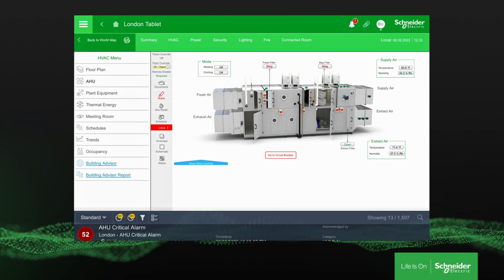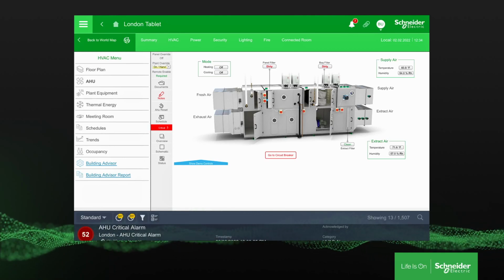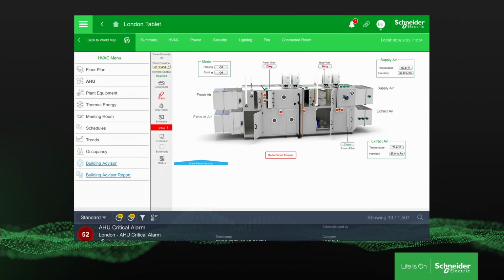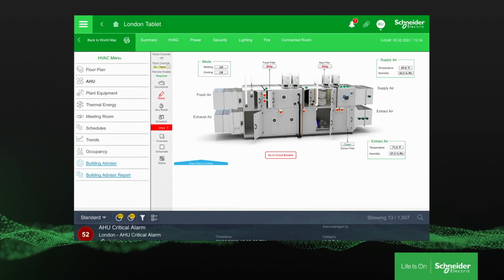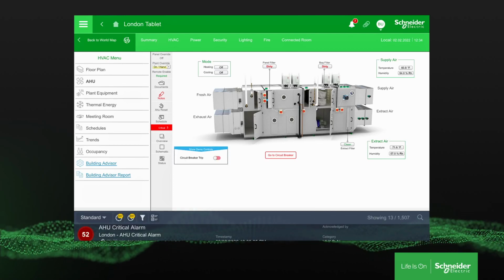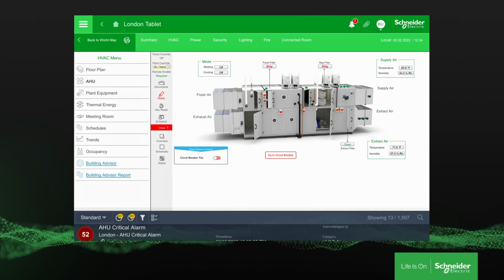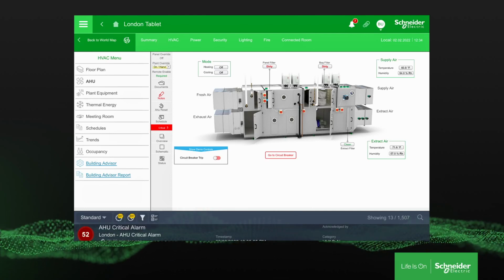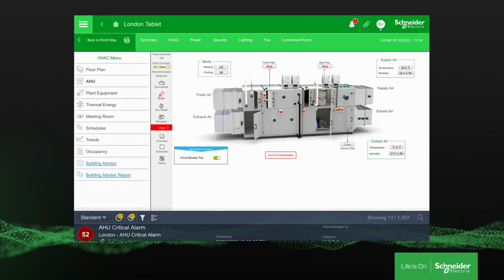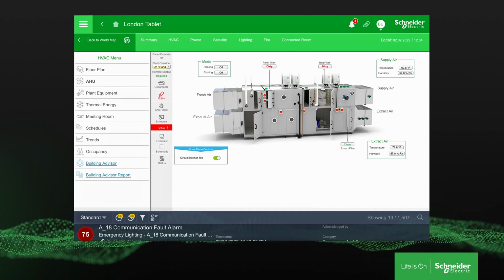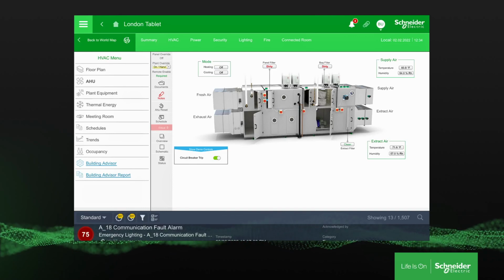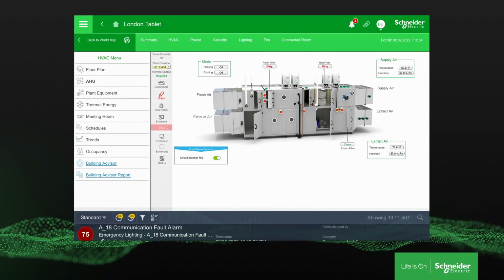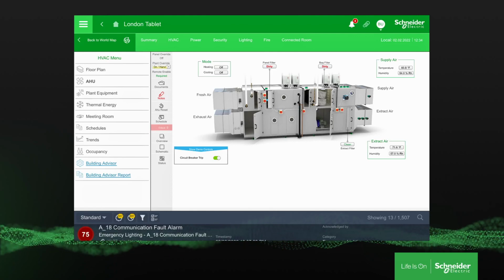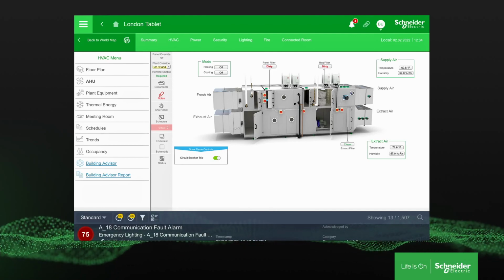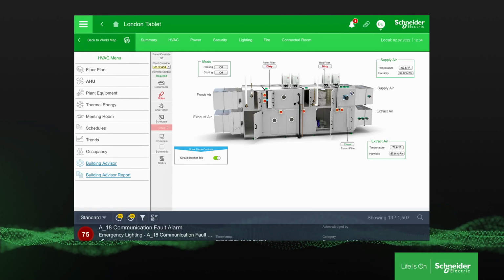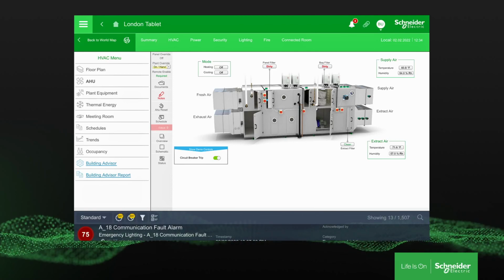Powerful alarming functionality and graphics deliver fast diagnosis and response to any issues that arise that could affect comfort. For instance, I can now clearly see the source of the critical alarm from the air handling graphic is a tripped circuit breaker. The facility manager can send staff to inspect the unit and reset the breaker. Now I'll simulate resetting the breaker and the air handler. With that addressed, EcoStruxure Building Operation updates the graphics to make it evident that the air handler is operating again. Though I noticed the air handling needs some maintenance on the panel filters.